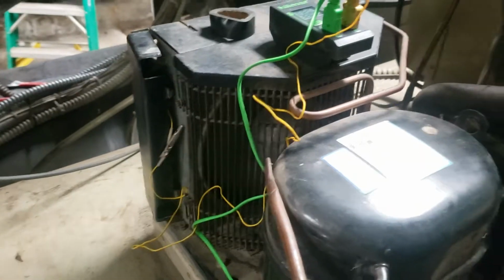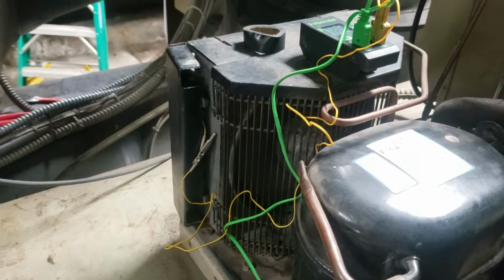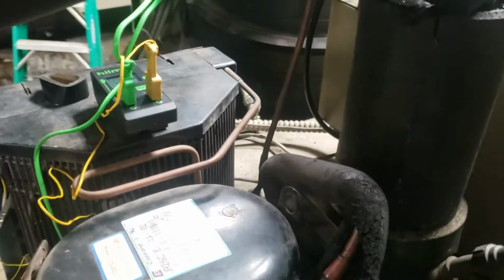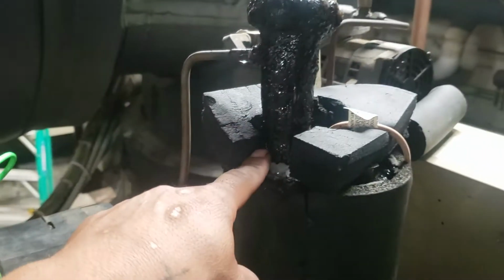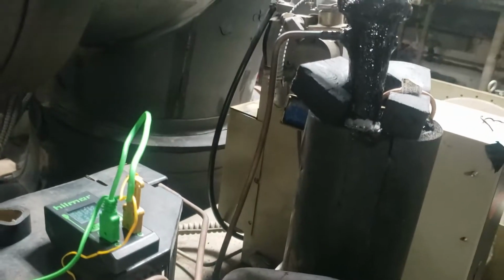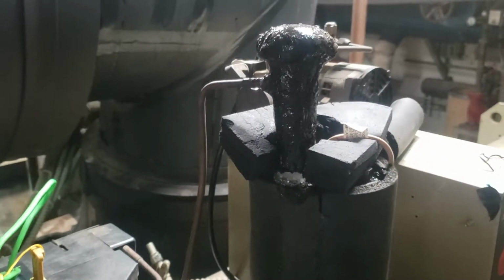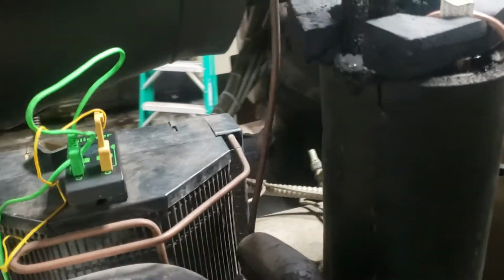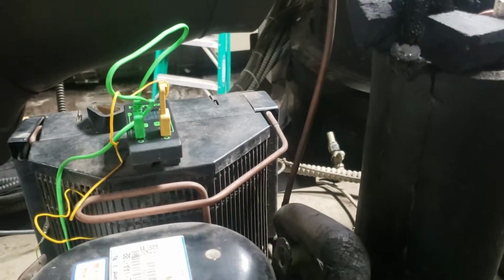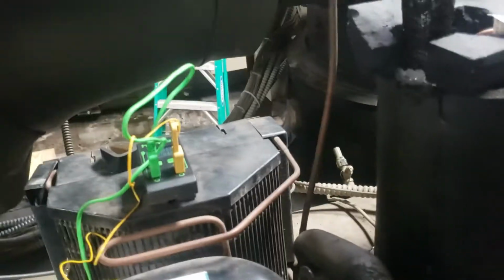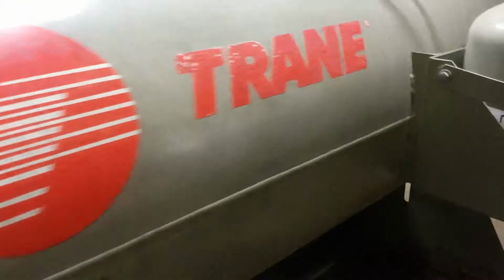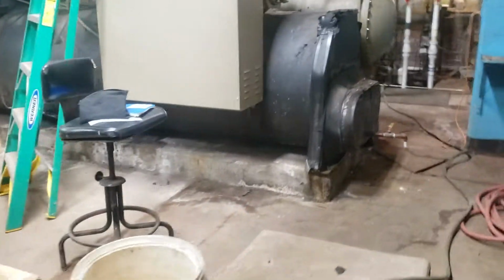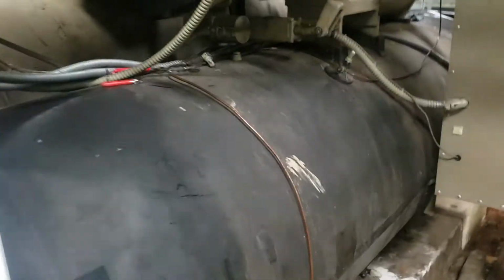And what they want to see is a subcooling of 5 to 15 if the unit's properly charged. And right here, this is your liquid line, this is the metering device, and down here, after the metering device, they want to see a temperature of 0. And sometimes you're okay if you read between -5 and 10 degrees. You should still be good. But anything other than that, you've got some kind of refrigerant problem. So the next thing I did, I isolated my condenser refrigerant coming from my condenser right here.